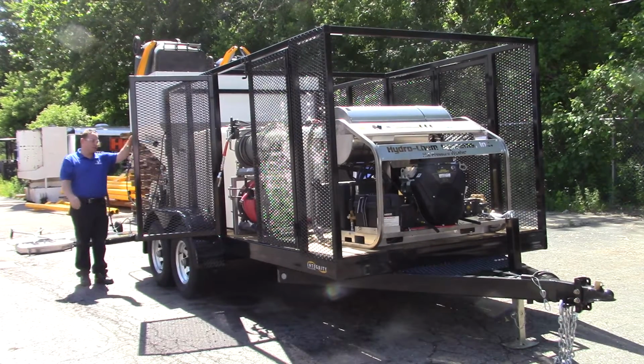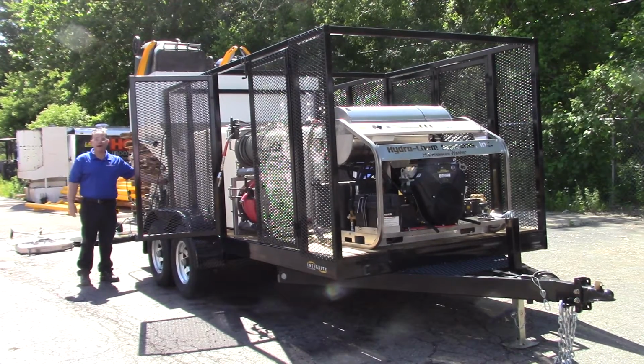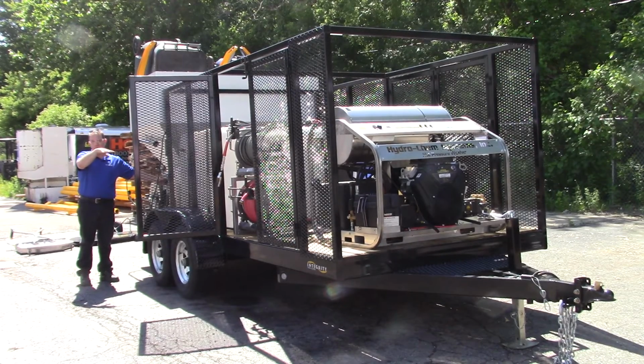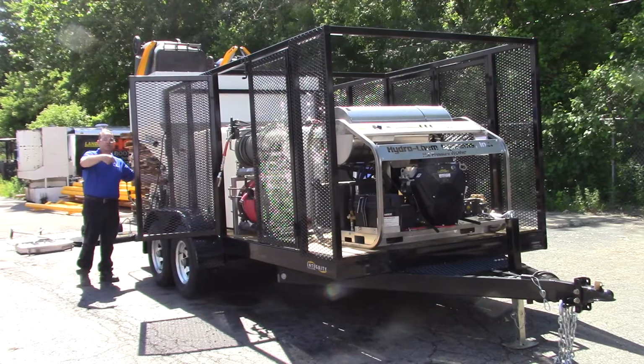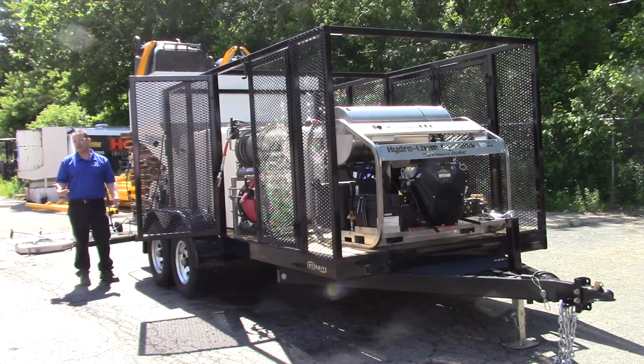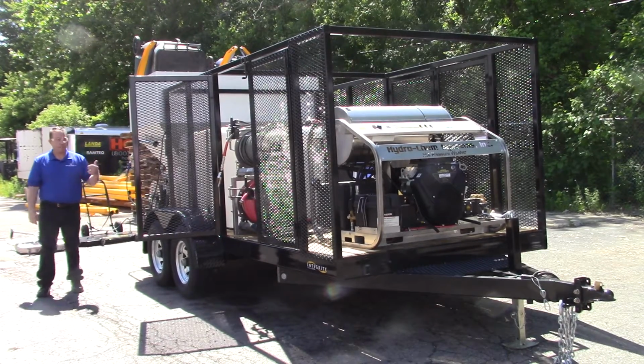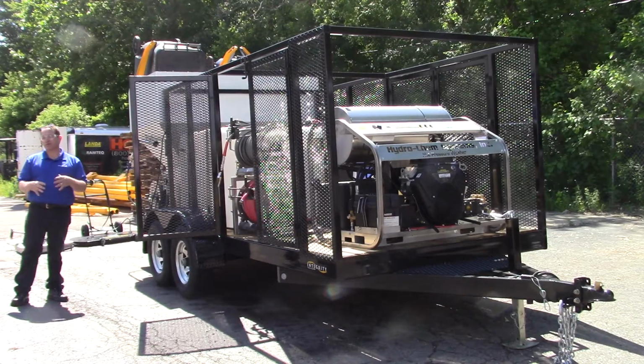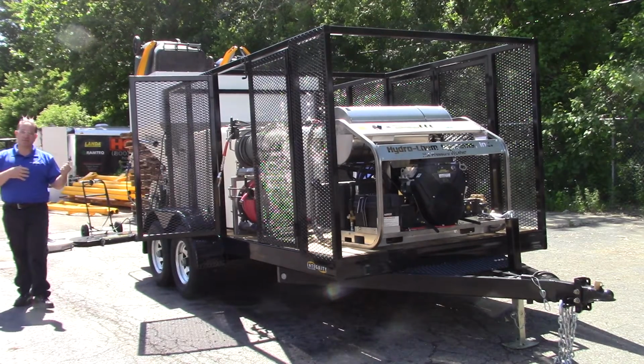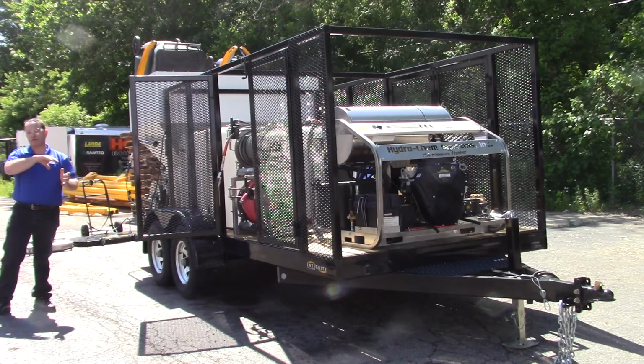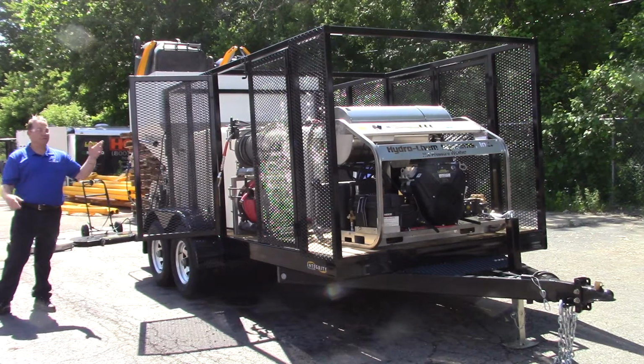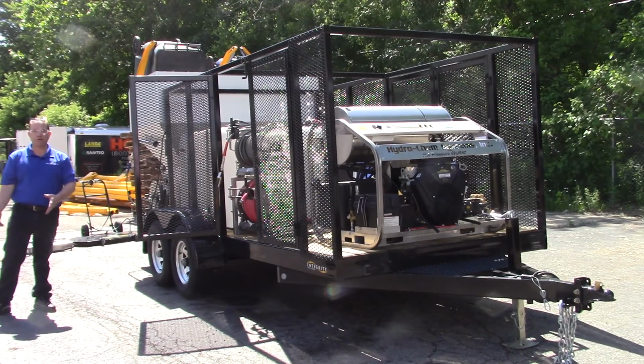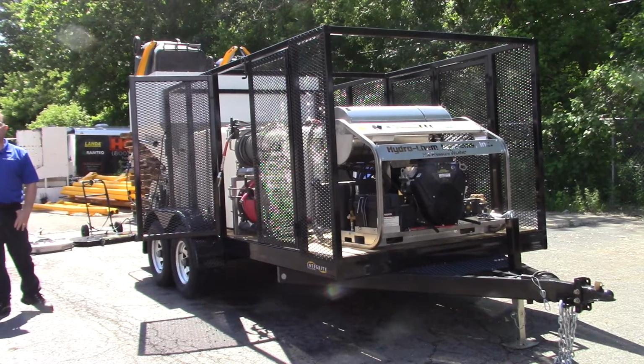They could actually leave the machine run, open the bypass valve here. There's no pressure on the pump or motor at that point, and they can actually go from stop to stop without worrying about what they call heat of bypass. That's when, with a positive displacement pump, the water has to go somewhere. So if you shut the gun off, the job of the unloader is to re-divert that water, normally either back to the pump on a small portable unit, or in this case back to the water tank. So it circulates that water and prevents the heat of bypass from building up.